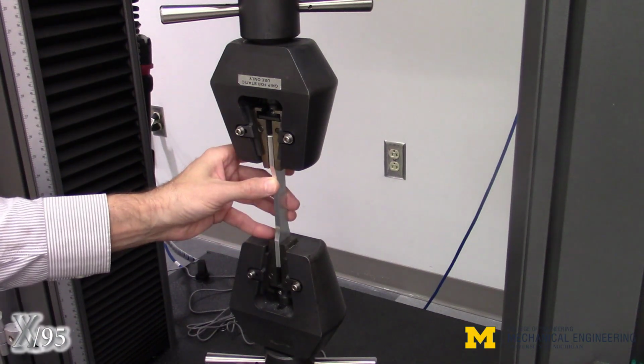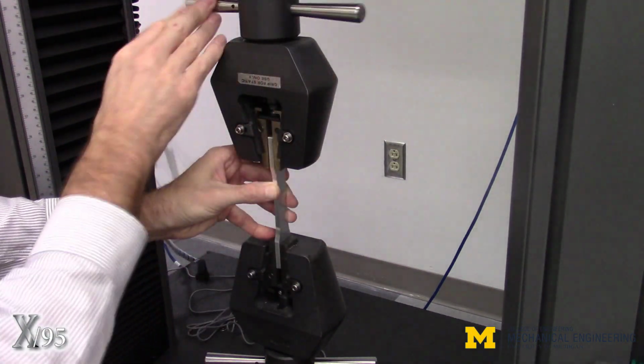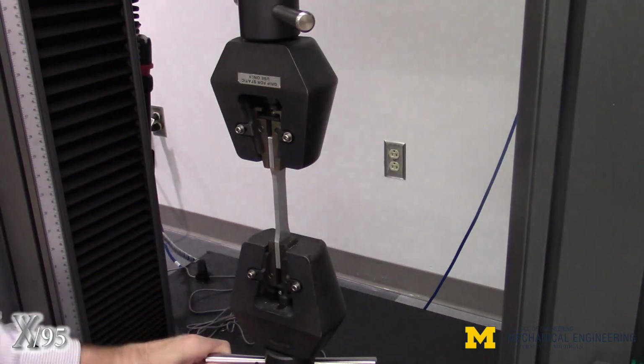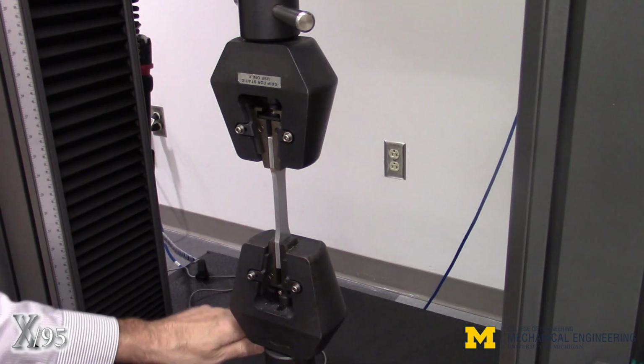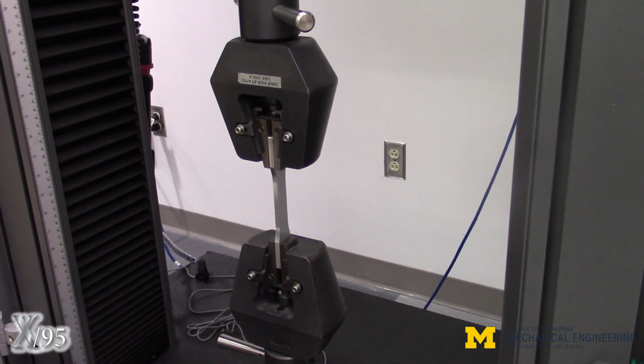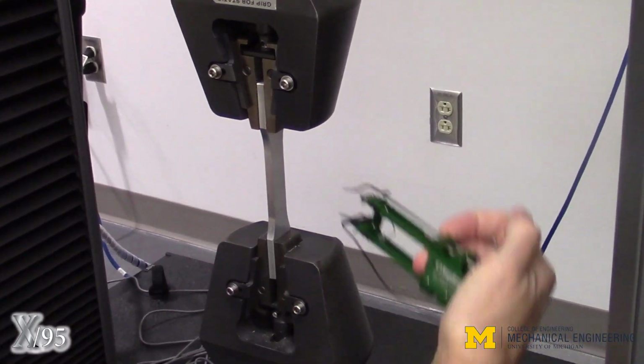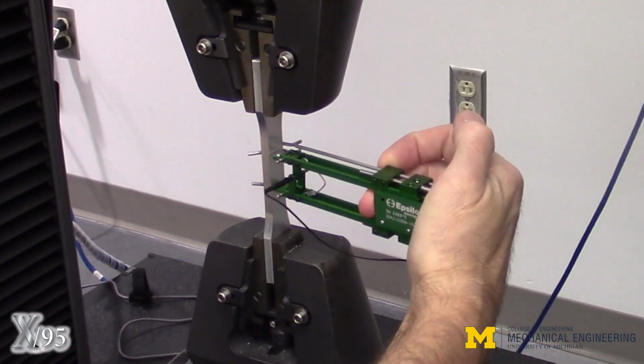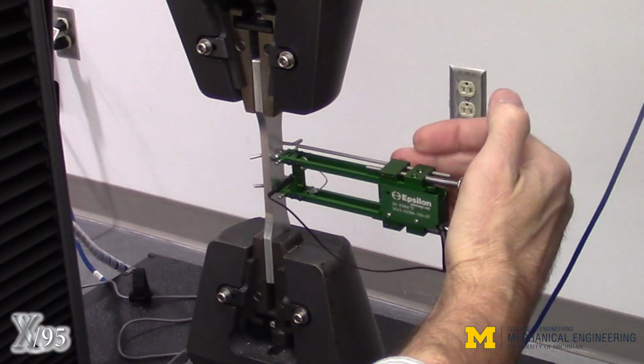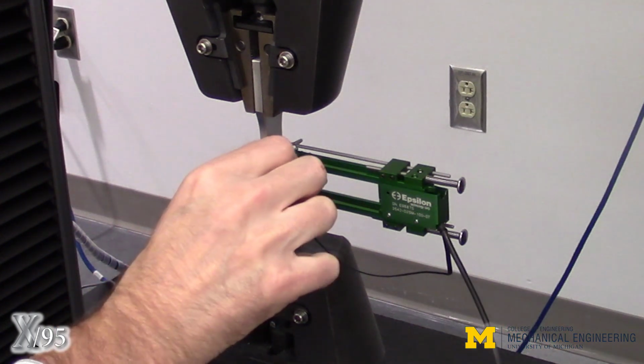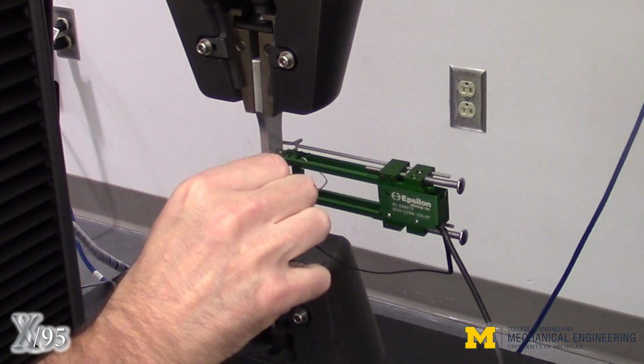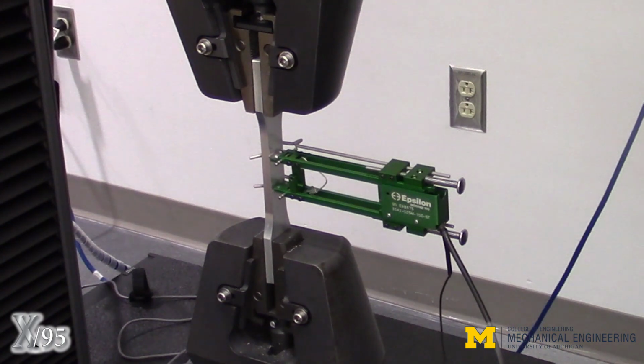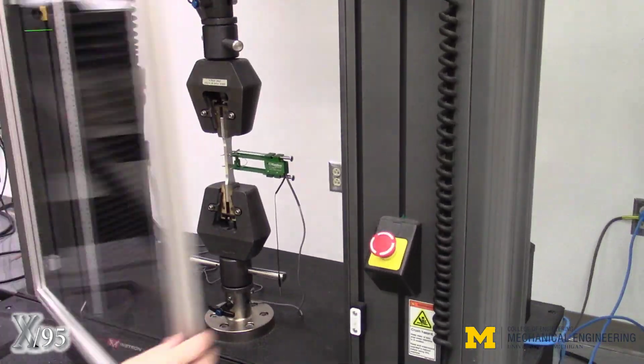Install the aluminum dog bone into the grips and tighten until firmly snug. Be careful not to over-tighten, which may damage the grips. Next, gently install the extensometer near the midpoint of the specimen. Once seated, carefully remove the calibration pin and allow it to hang. When done, close the guard door.